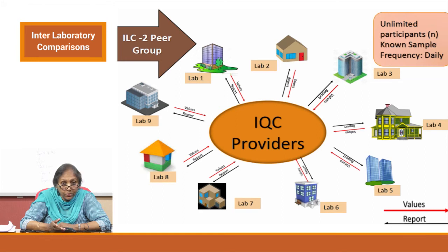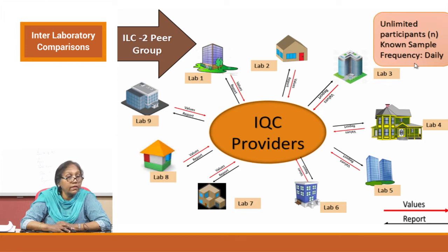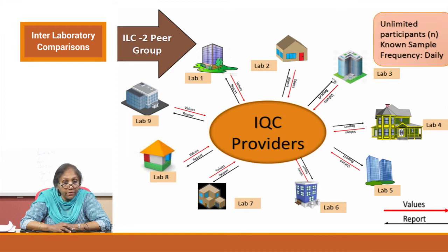The second type is the peer group. Again, there can be unlimited participants, but the sample is a known sample — that is the difference. Frequency is daily: you analyze the sample daily, find the mean, and the values are fed to the QC provider. At the end of the month, they give you a report on your analytical performance.